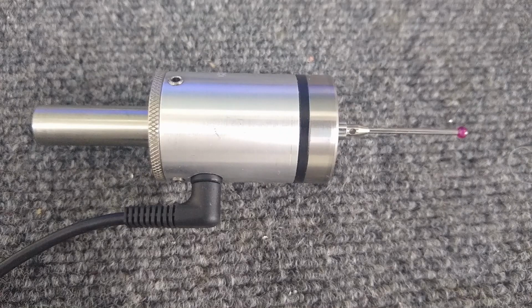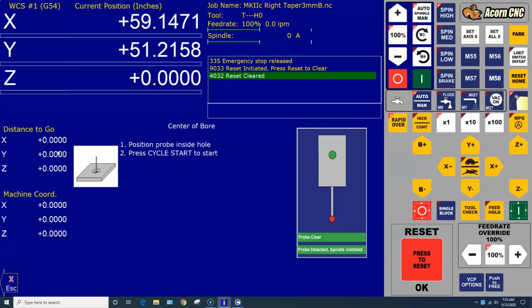and with the KP-3 plugged in, make sure the plug is fully seated. Again, make sure you get that plug all the way in. There's two detents. You want that plug face all the way up against the probe body. Manually trigger the probe by gently touching the stylus to trigger the probe and observe the probe state indicator graphic on the screen. If the probe is configured and wired properly, the probe tripped graphic on the screen will indicate that the probe has been tripped.